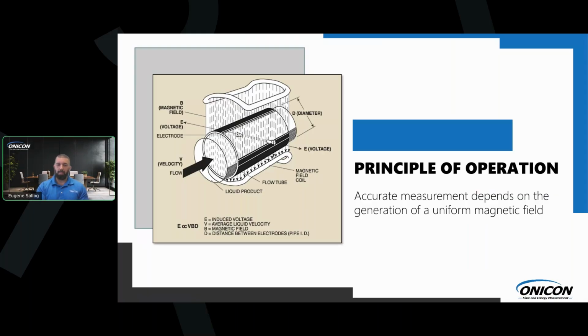You might see that on a spec every once in a while, where an inline mag spec says it has a stainless steel flow tube. That's what it's referring to. It doesn't necessarily mean it's a stainless steel bodied meter, just that the flow tube on the inside is stainless steel, and of course the liners on the inside. Also, we are capturing the whole cross-sectional area of the water flow, which makes it extremely accurate and reliable.